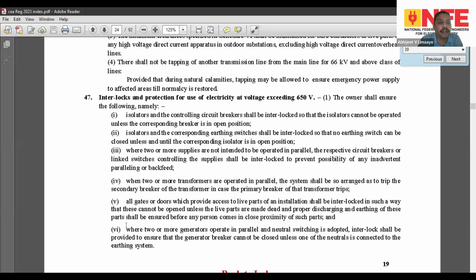typically multiple generators, you have to balance it out in a very particular way, because two generators which are not supposed to be started together should have an interlock, again what I said, break before make. So please open the supply and then make the other supply. There always has to be a small transition delay, it could be a few milliseconds, and the equipment downstream also has to withstand it. Because of this fundamental, a lot of times you might have to install emergency supplies downstream to comply with this regulation.